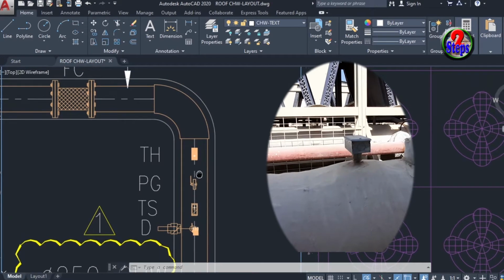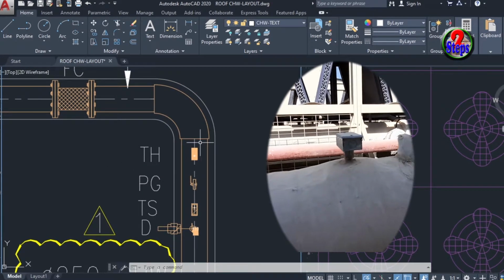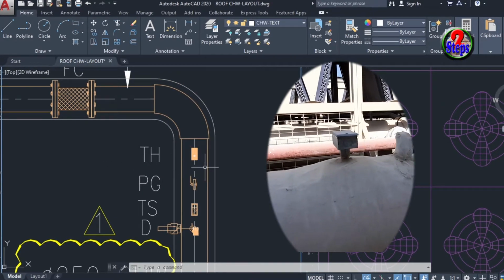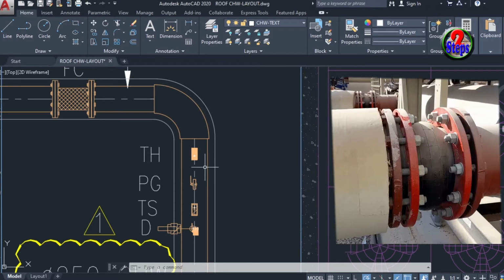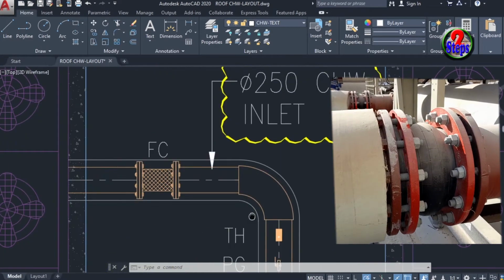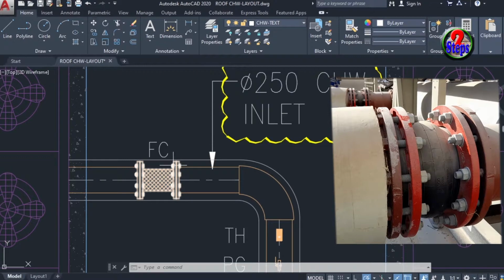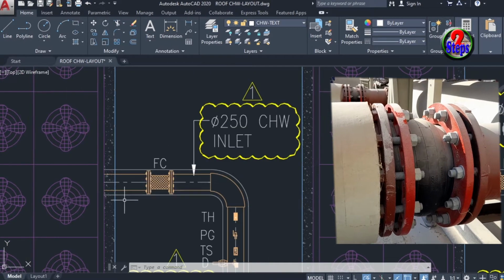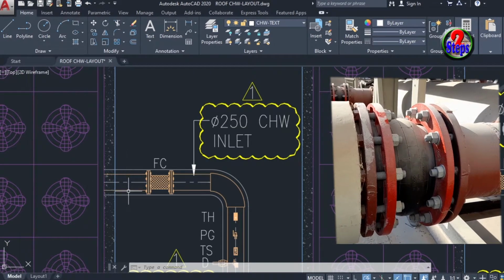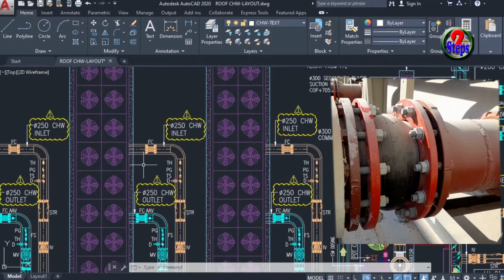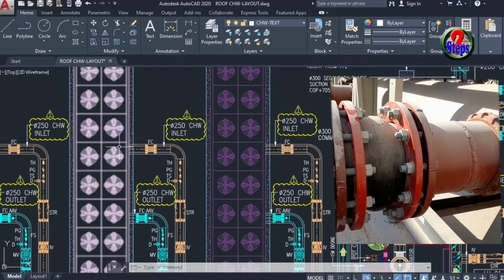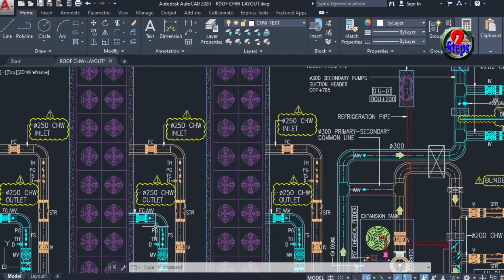After that, this point is for thermostat connection. Its drawing symbol is TH. At the end, the flexible connector to connect to the chiller inlet. The drawing symbol is FC. It is also called a rubber connector. It is very useful to isolate the machine vibration from the pipeline.